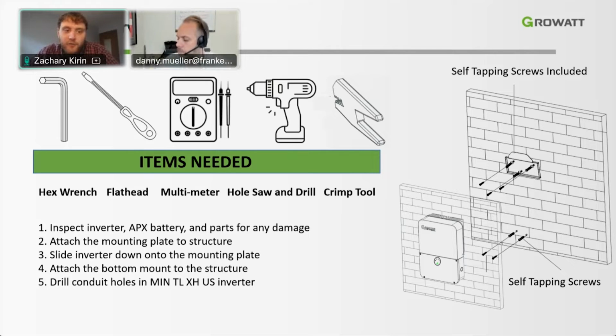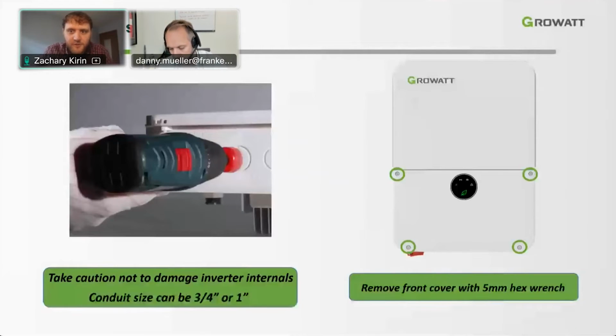Before you mount the inverter to the wall, I do recommend, if you have an idea of where the conduit holes for the inverter are going to be, go ahead and drill out those conduit holes first and foremost. It's easier to do this on a table or with the inverter still outside of the box and not installed. When you are drilling out the conduit area with the hole saw, it's important not to damage the inverter's internals. It's pretty easy to go a little bit too gung-ho with the hole saw and go through the outside housing of the inverter and penetrate into the inverter too much. We want to take caution not to do this. Just use your hole saw normally, and you'll be able to screw out a port that is either a 3/4 inch conduit hole or a 1-inch conduit hole.